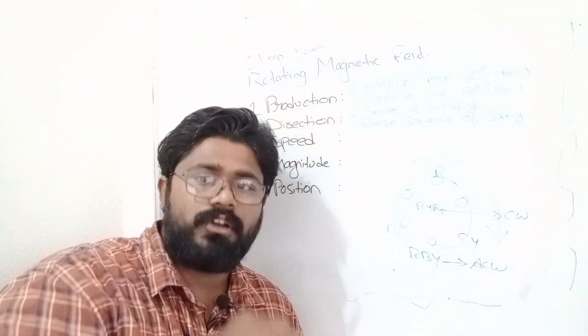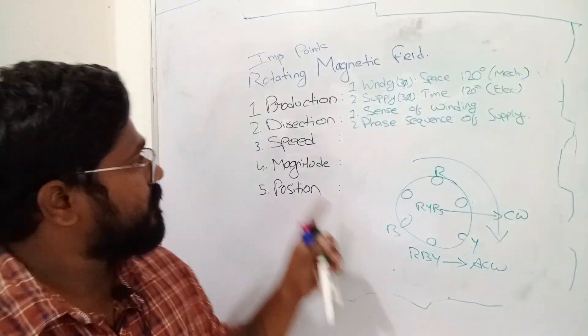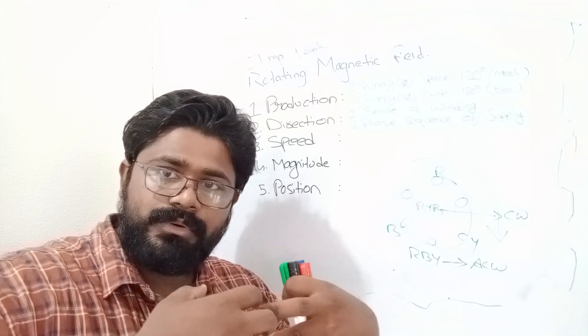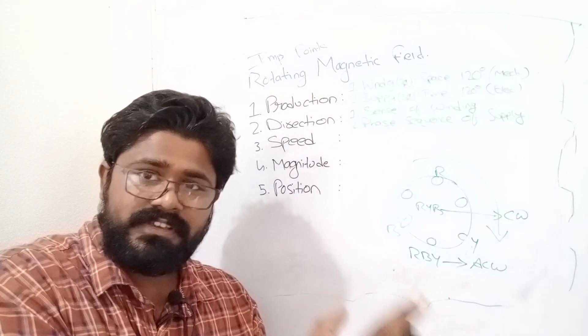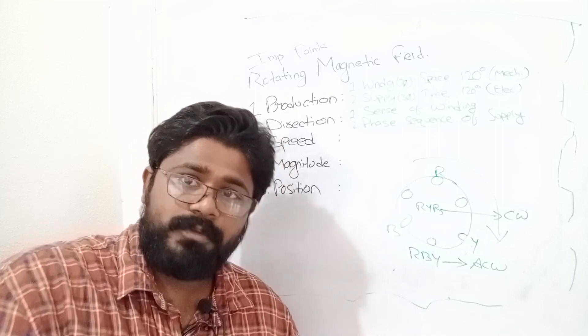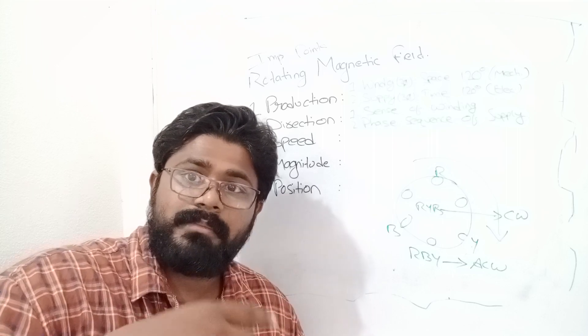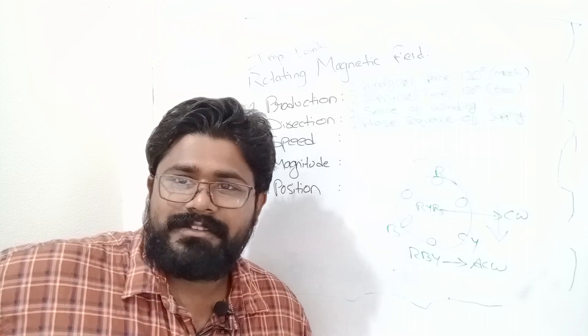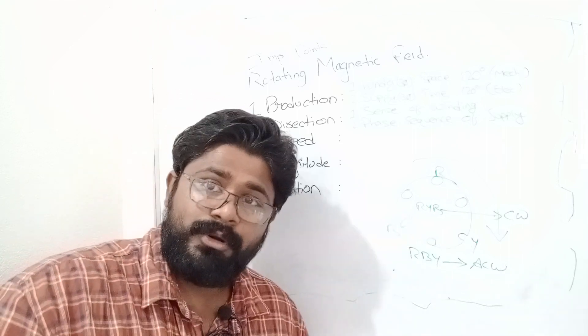The direction of the rotating magnetic field is dependent on the sense of winding and the phase sequence of the supply. RYB corresponds to clockwise and RBY corresponds to anti-clockwise direction. If we already have a machine constructed, we can change the sense of winding. Since those are just wires, we can also change the supply connection to reverse the direction of rotation.